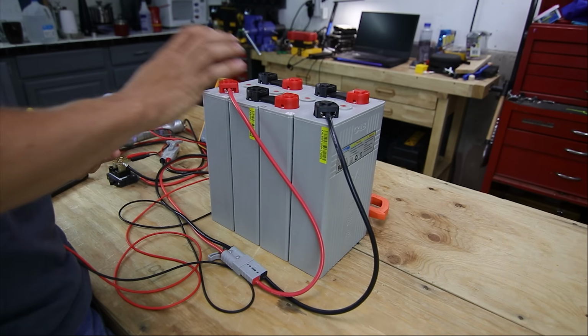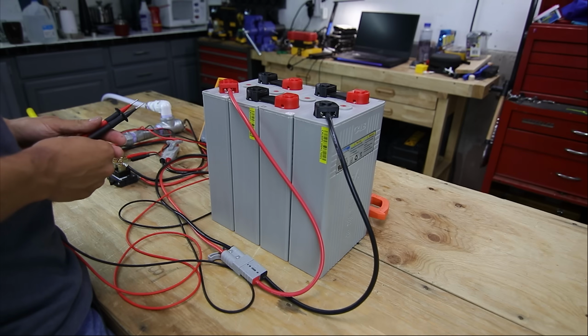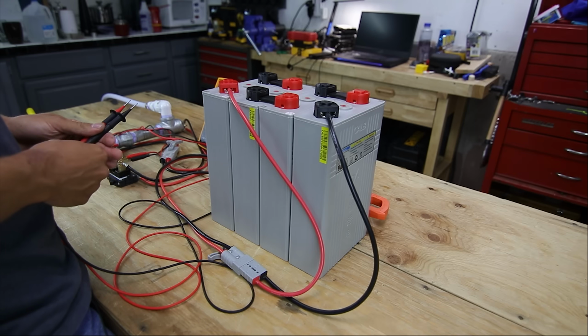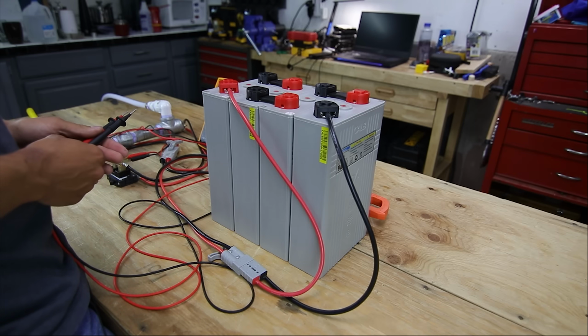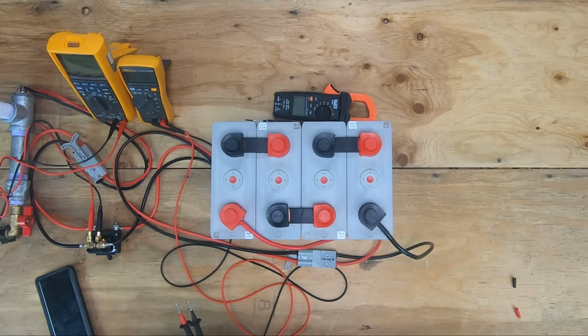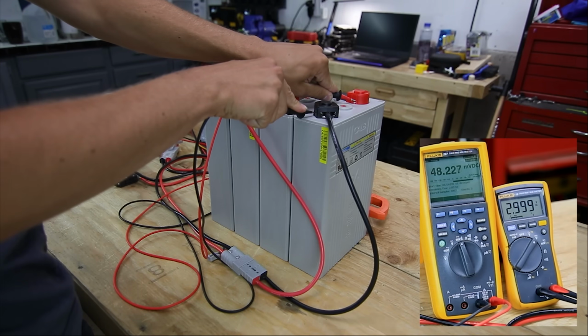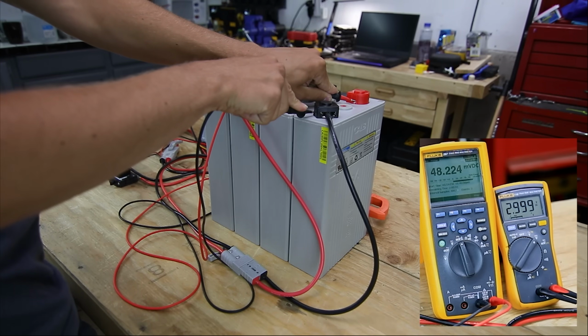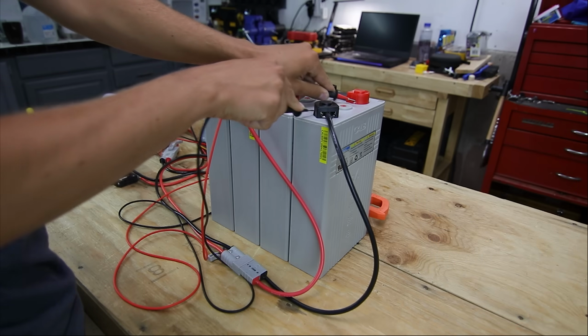Now I'm actually going to bring these batteries to 2.5 volts, which I would not recommend doing. That's a very low state of charge and puts real abuse on the batteries, but they're new so they can take it. I will be affecting the life of these batteries though. We're at 2.999 volts, so sample 4081 is what I'm calling the 3 volt reading.